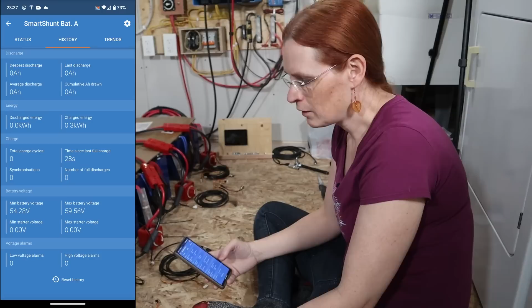Well, it's still 300 watts. If there's a big cell deviation where the balancing would normally need to run more often, you could argue that's more of an issue with the individual cells and not the BMS, which is strictly what we're trying to test. The average cell voltage is 3.53, and we cut off at 3.6. So if I was to do this test again, and I don't think I'm going to do it anytime soon, I think what I'd have to do is charge until I hit a defined, consistent delta cell voltage, say 0.005 or something like that.